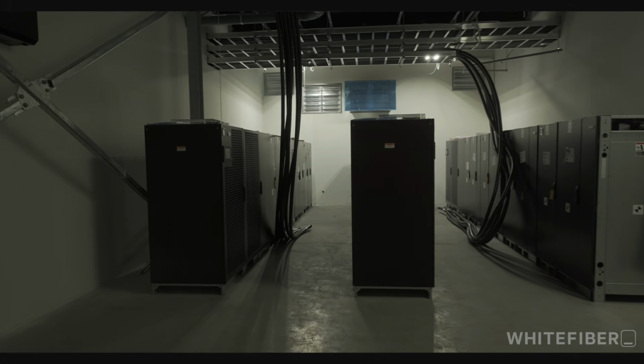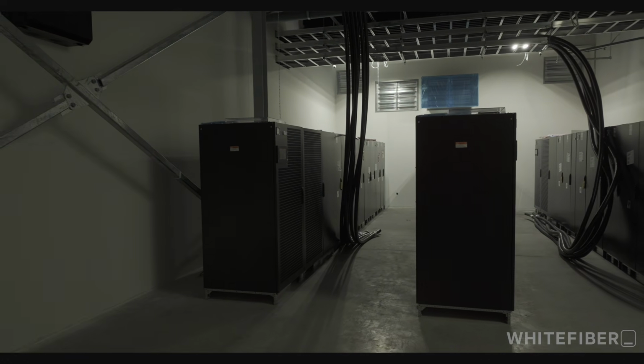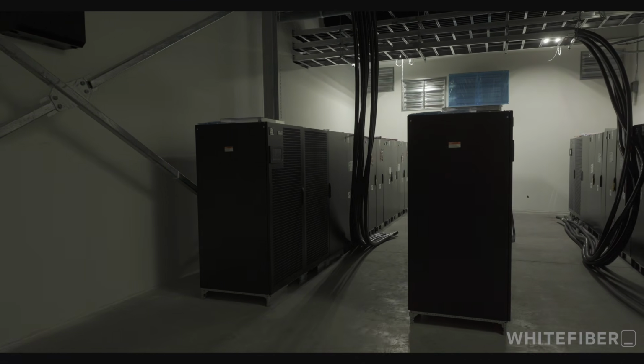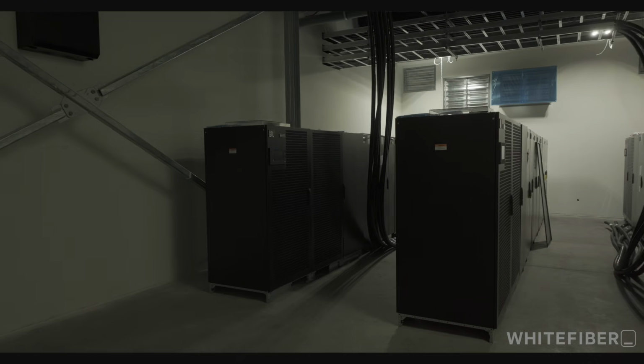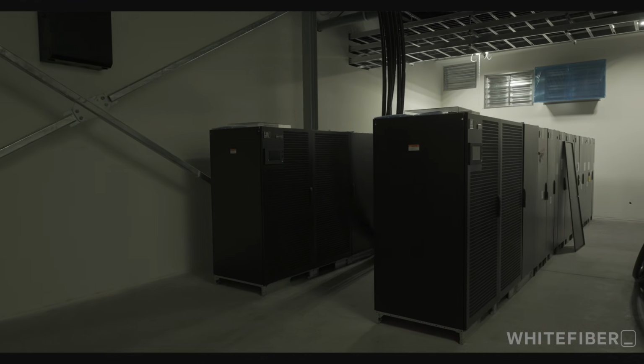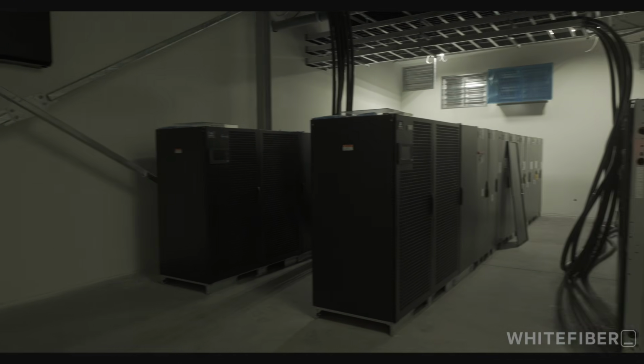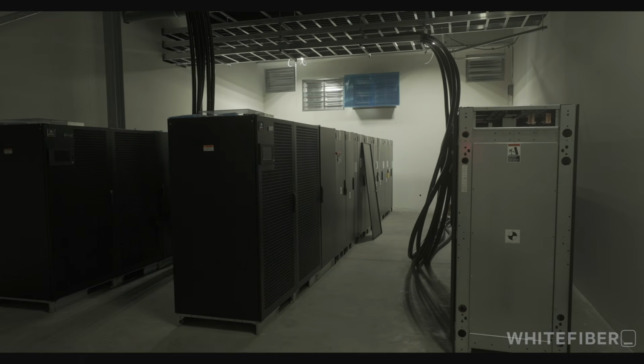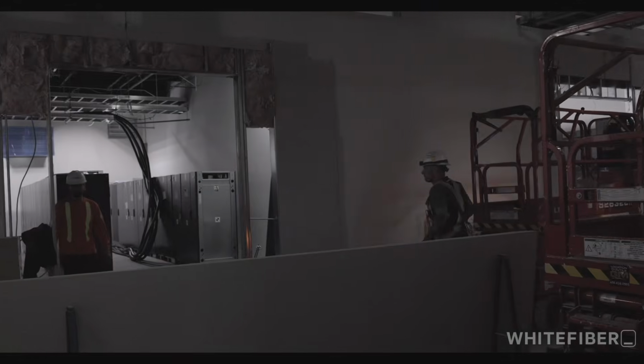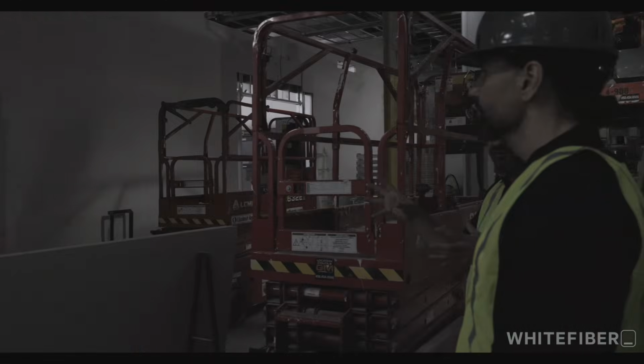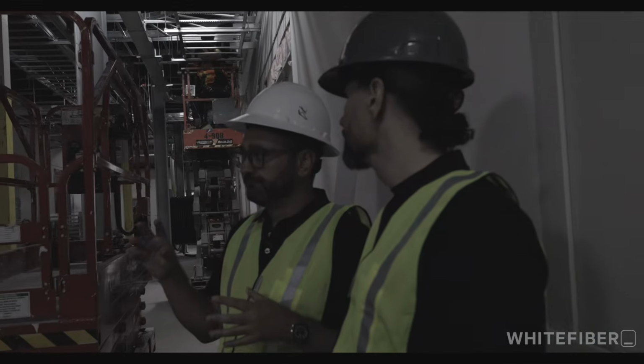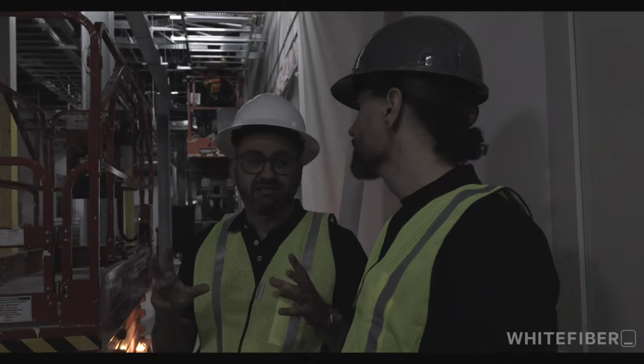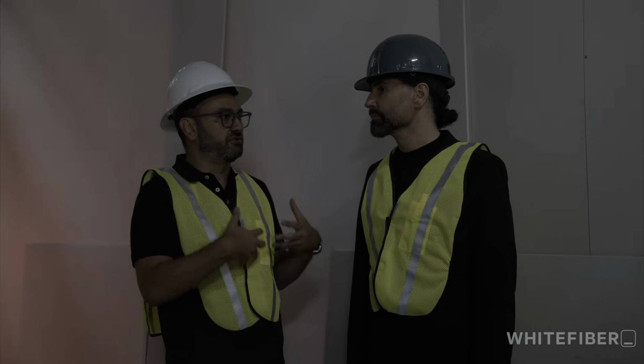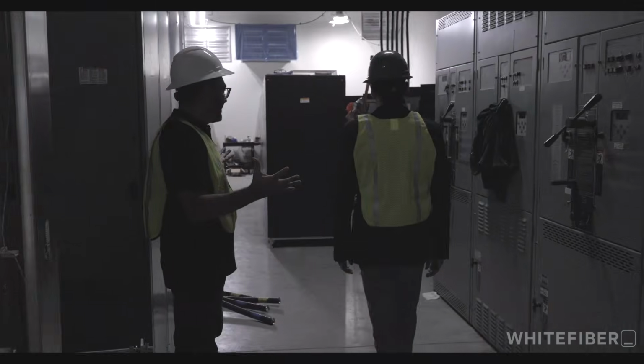Over here we have battery rooms. So ABC battery rooms, 3 feeds again. Only need 2 to be live for the installation to be working. So we can maintain one of them, take one of them down at any time, and the installation is still up and running. And the batteries, again, really only for the 10 to 15 seconds it takes for the generators to start up and stabilize. So here we have the battery room.